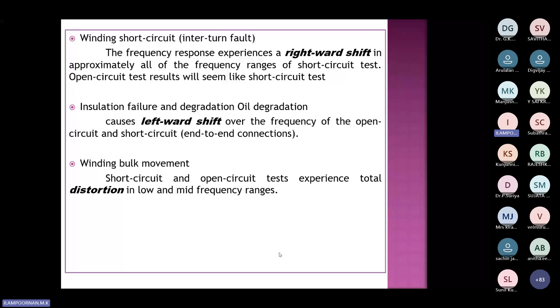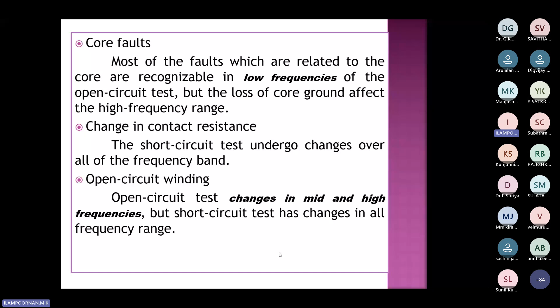So the core fault, of course, this is the very beauty of it. If there is any grounding fault or any short circuit, you don't know, because we only check winding short circuit. But what happens is sometimes the core will get earthed. That is a problem in the core. So you will have a spark between the core laminations. So those things can be identified with the FRA. That's one of the beauties of the FRA. And the open circuit, of course, you will have a change in the mid and high frequencies.